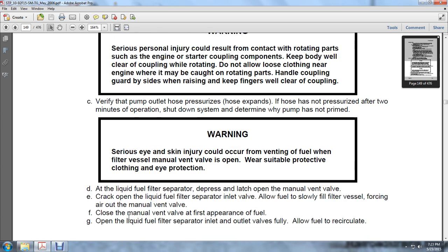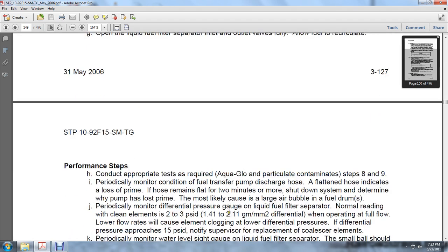At the liquid fuel filter separator, depress the latch and open the manual valve. Crack open the inlet valve of the fuel filter separator and allow the fuel to slowly fill the filter vessel, forcing air out of the manual vent valve. Close the manual vent valve at the first appearance of fuel. Open the liquid fuel filter separator inlet and outlet valves fully. Allow the fuel to recirculate.